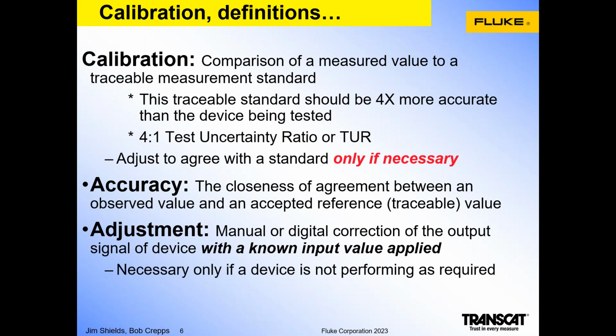Calibration is by definition the comparison of a measured value to a traceable measurement standard. So the measured value in a process example would be the milliamp signal, for example, that's being measured as the output of an instrument device. And the traceable measurement standard would be the calibrator with a certification that's making that milliamp measurement.